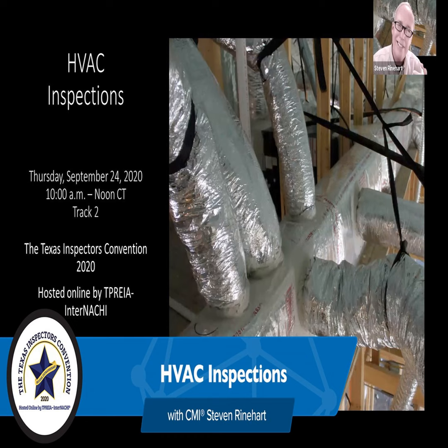For a heating, I usually see when you first crank that thing up, you can easily get 40 degrees of heat coming between return, and I use the closest supply. I want to see as close as I can to that air handler, and I'll try to figure out the closest one and give me some standards. If there's a difference between the closest register and the farthest register, it's not the air handler, it's not the unit, it's the distribution system that's an issue. And I'll look at that when I get to the distribution system.